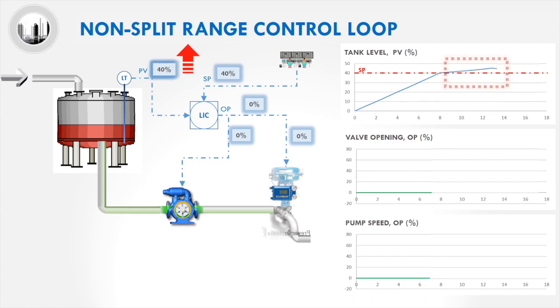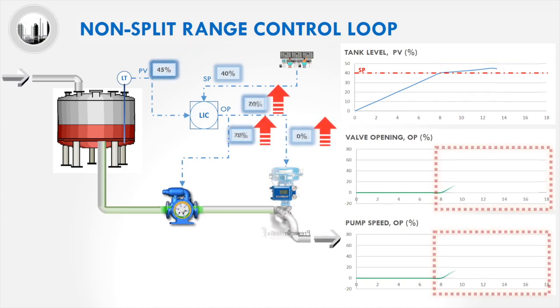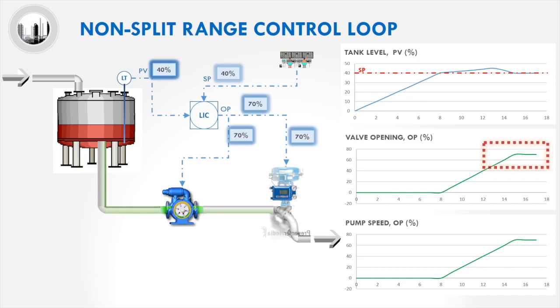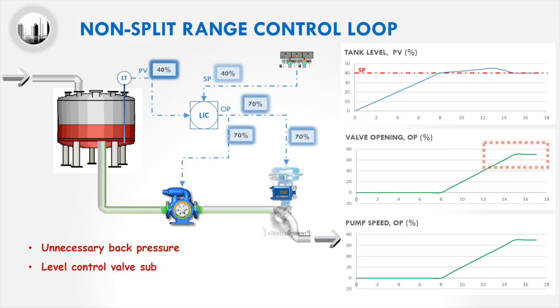Once the tank level increases above the set point, both the control valve opening and pump speed will increase. This will cause the tank level to slowly return back to the controller's set point. One important observation is that the control valve will be partially open even after the process has stabilized. When the control valve is partially opened, it will create unnecessary back pressure to the pump. Another disadvantage is that the control valve is subjected to more wear and tear as it is continuously throttling whenever there is a process disturbance.